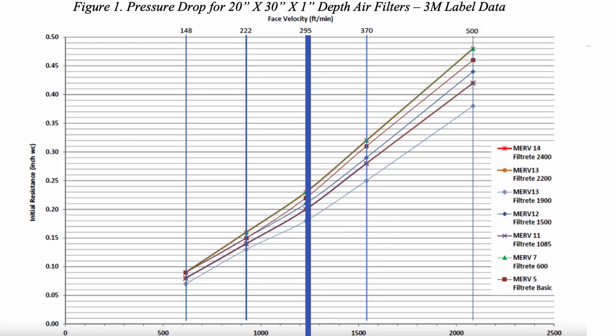So this is a chart that actually shows the pressure drop for a 20 by 30 by 1 inch 3M filter. You'll see that there's different MERV ratings here. And the higher the MERV, the more the filter is going to capture. So if we're at a 3-ton unit, we want to have 1200 CFM of air. This is the solid blue vertical line that I've put here. It's roughly 1200 is where it's put. You'll see that based on a clean filter, at 1200 CFM, for my lowest MERV filter I'm going to have right over 0.15, so it's like 0.17. For my highest MERV filter, I'm going to have a 0.23 pressure drop. That's with the filter clean. So filters affect pressure drops. Again, a clean filter, if it's too tight, you're going to have a large pressure drop.